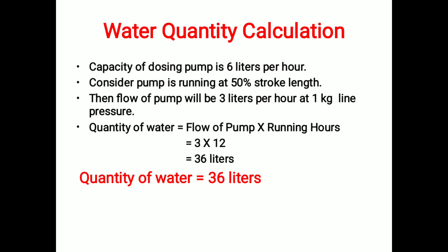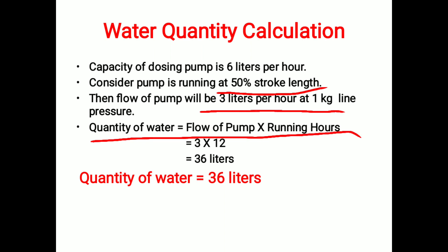The pump is running at 50% stroke length, that is 50% of its total capacity, which means it is running at 3 liters per hour at 1 kg line pressure. The quantity of water is calculated using the formula: Quantity of Water = Flow of Pump × Running Hours. The pump flow at 50% capacity is 3 liters per hour, and plant running hours is 12. After calculation, we get 36 liters — that is the quantity of water required.